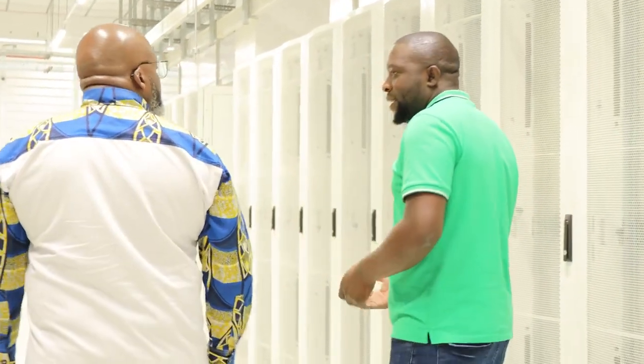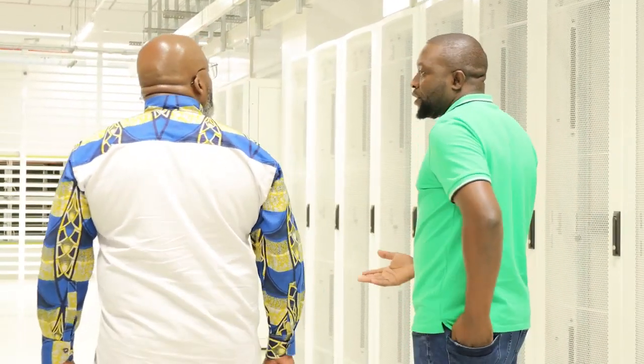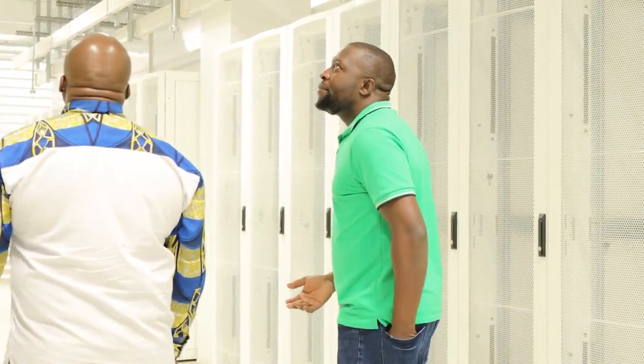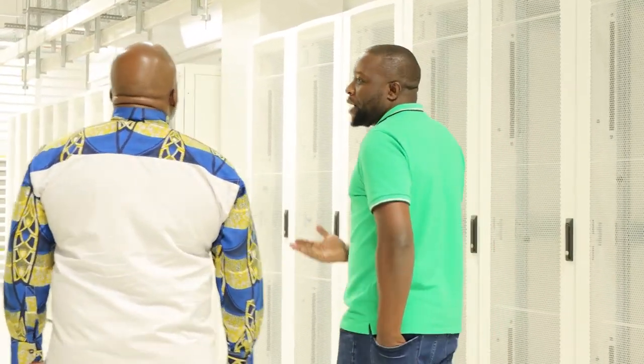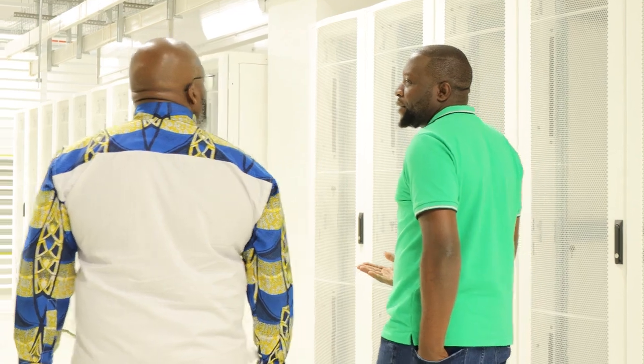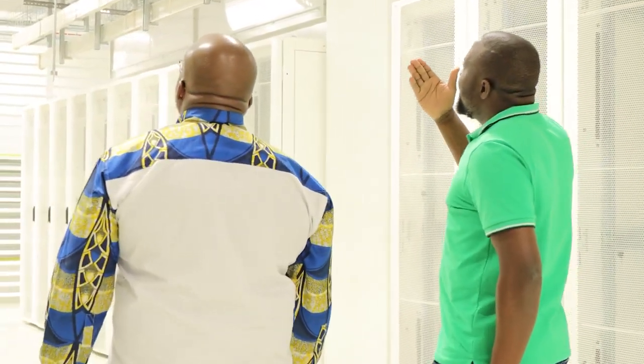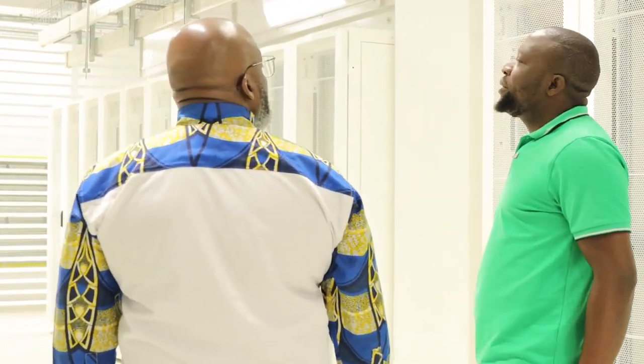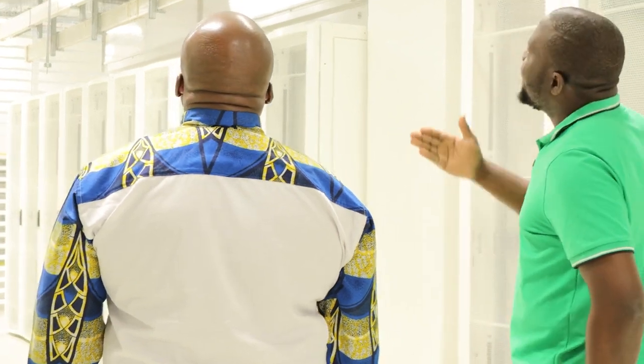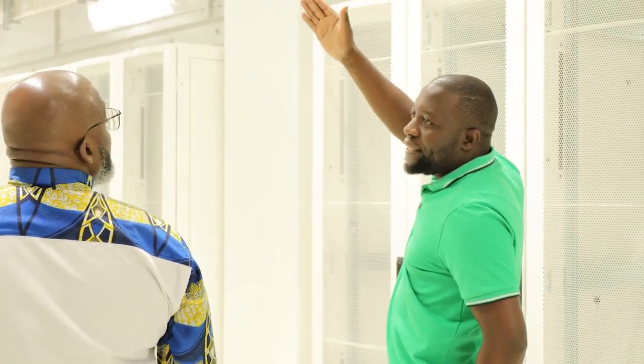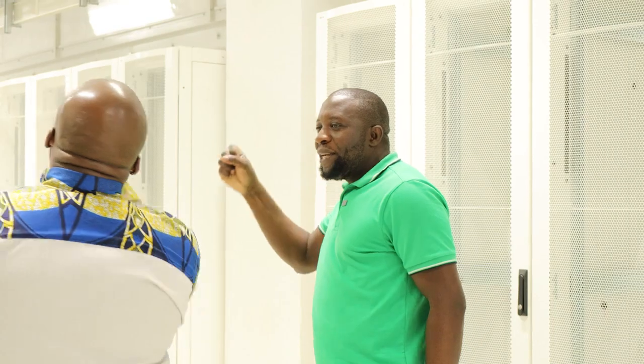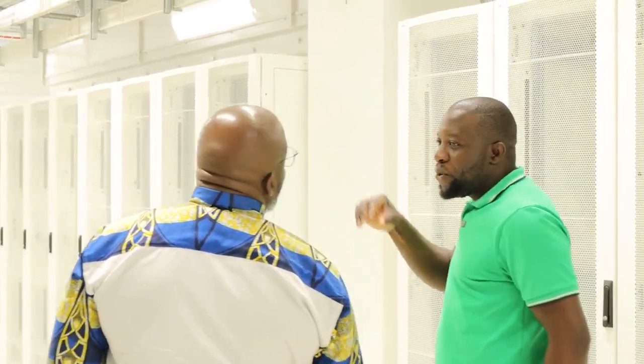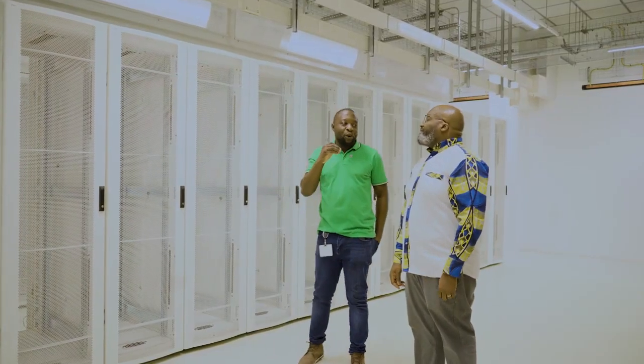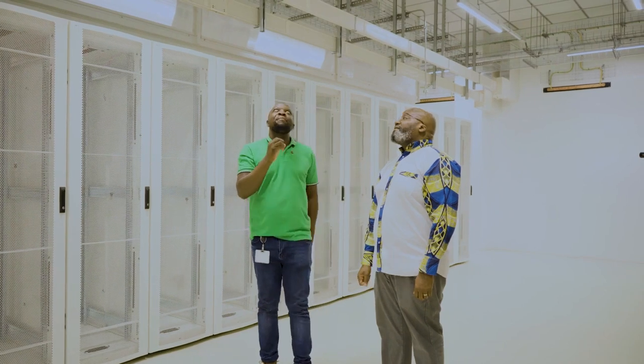In case of a fire outbreak in this room, we need to ensure the fire is quenched, and come up with mechanisms to ensure that. One mechanism we've used, and it's actually new technology in the data center right now, is water mist. We are cooling this data hall using water, it's water mist, very small droplets of water, up to 10 microns.